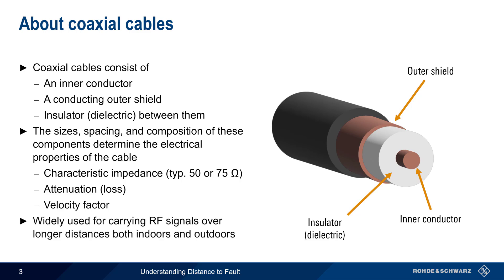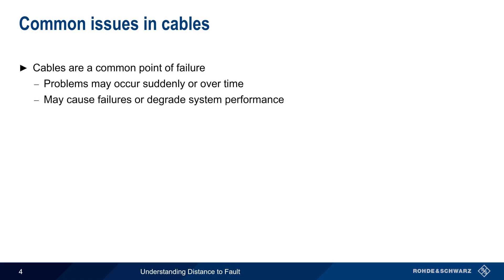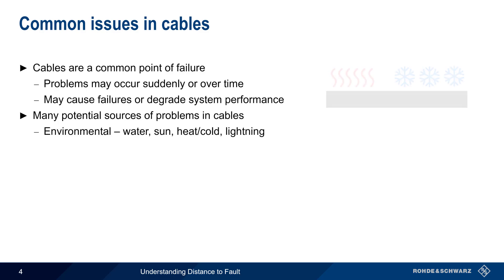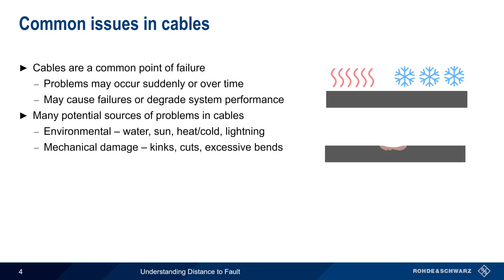When radiofrequency signals are conducted over long distances, both indoors and outdoors, this is most often done using coaxial cables. These cables are, however, a common point of failure within radiofrequency systems. Problems may occur suddenly or gradually over time, and the severity can range from complete system failure to various levels of performance degradation. In a non-laboratory environment, problems may be caused by environmental factors such as water, temperature changes, lightning, or mechanical damage such as kinks, cuts, or excessive bends.